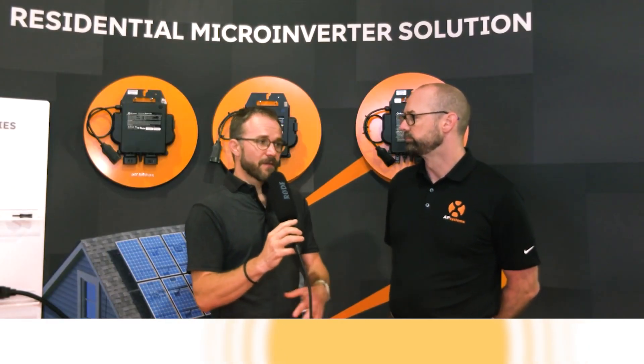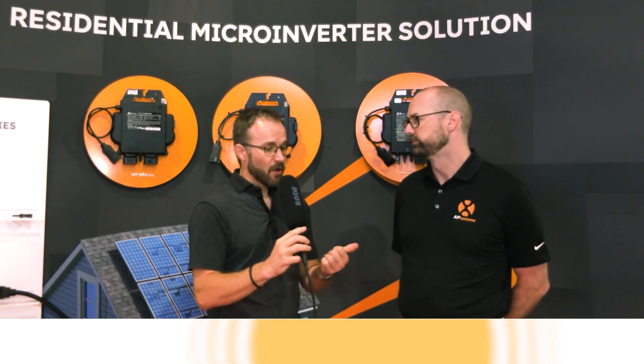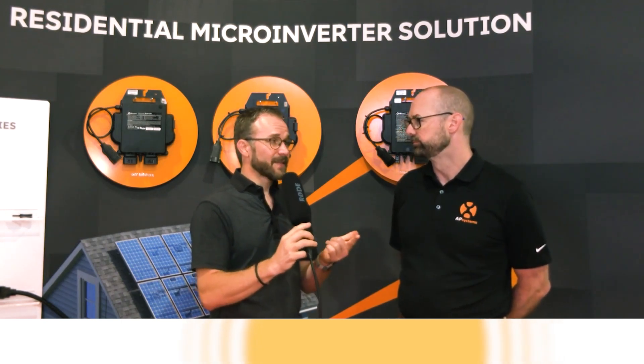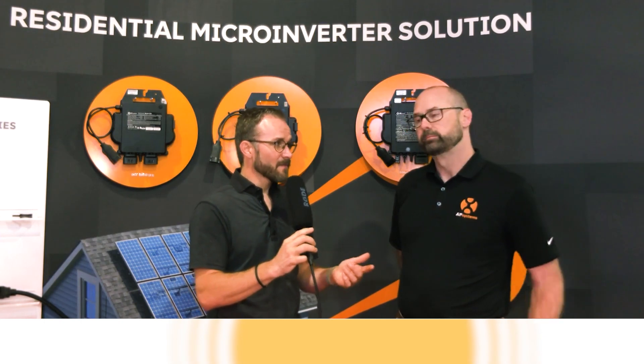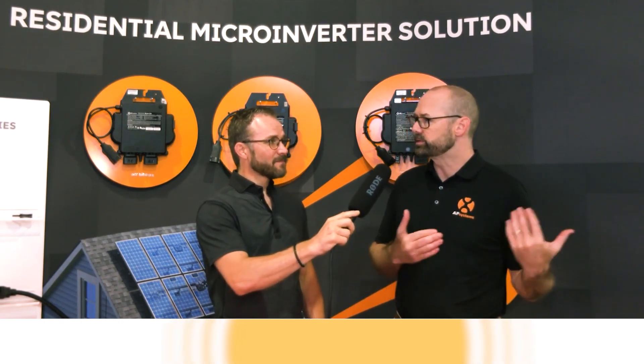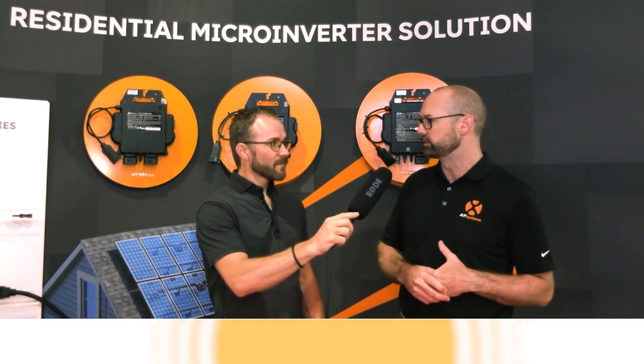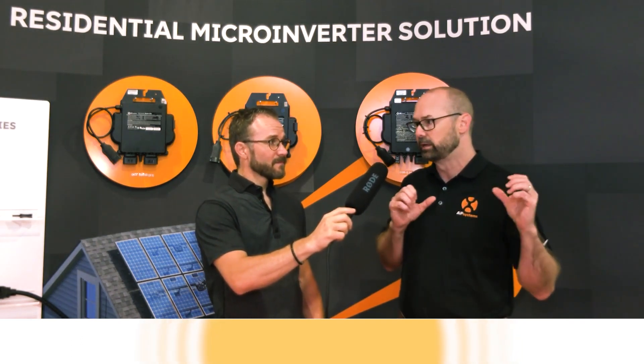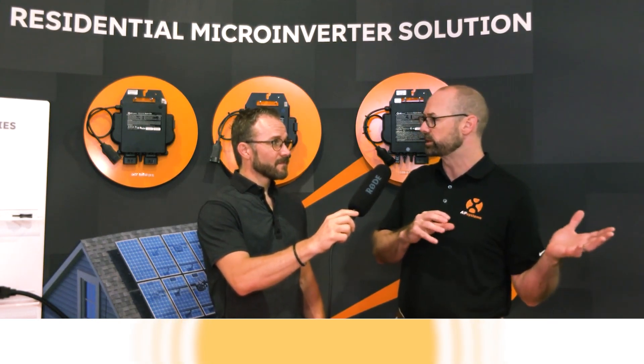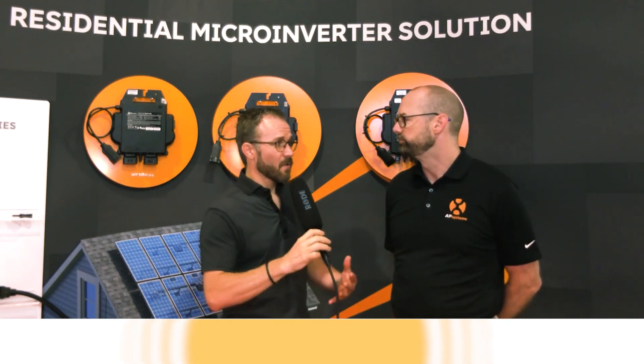On top of that, how many turns of the wrench, how many times are you installing a device? We're simplifying the logistics, cost, and labor. It also simplifies the balance of system — in a traditional system you've got all the DC home runs, and a micro inverter solves that problem. It reduces the overall balance of system required on the roof, which reduces the expensive electrician work. We really wanted this to be plug-and-play three-phase — it goes onto one trunk cable, you drop that into your sub-panel on a 30-amp breaker — five wires: one, two, three, neutral, ground.